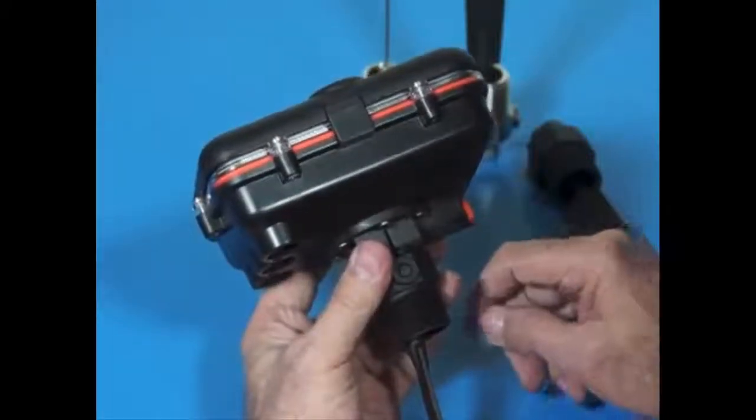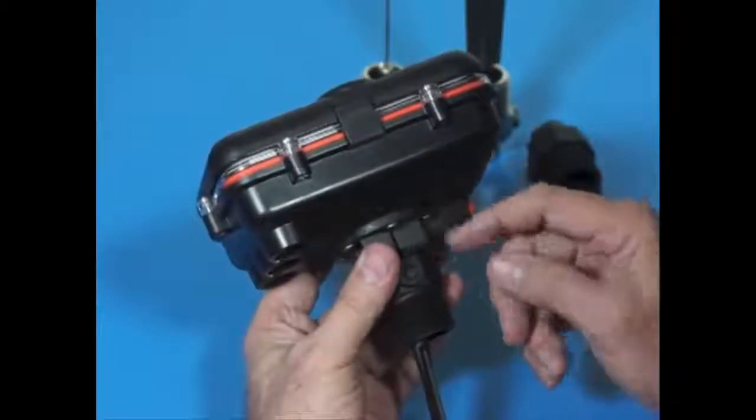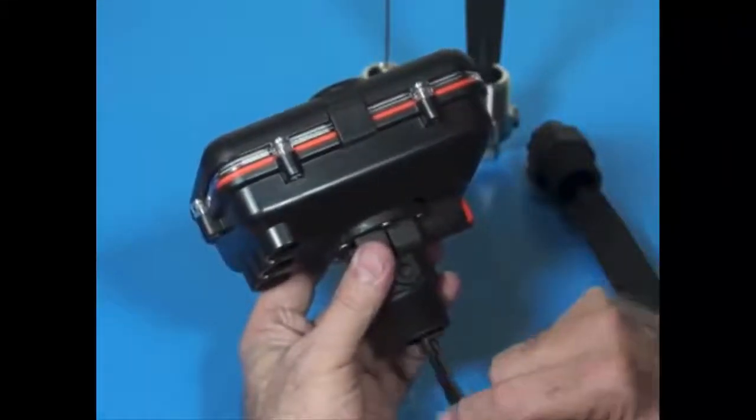There's a sensitivity adjustment system built into the F29, and it consists of a moveable magnet inside a housing here. You can wind this out to increase the sensitivity of the paddle to low flows.